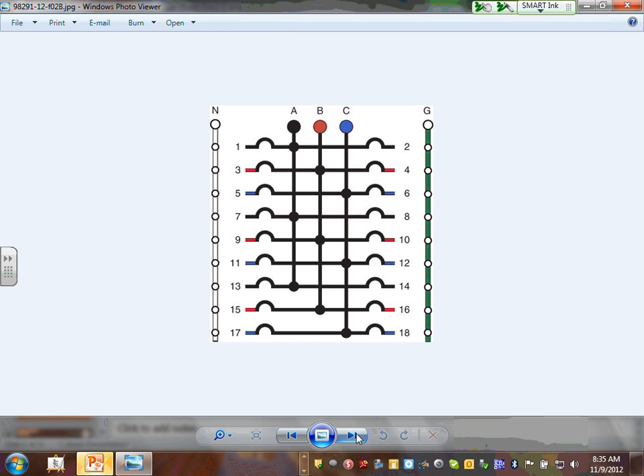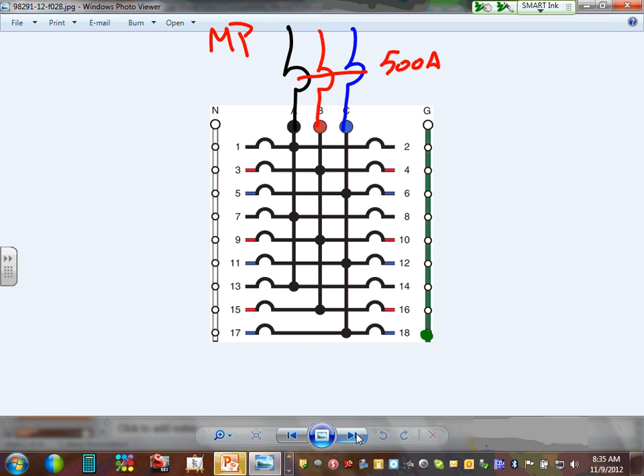Let's put a circuit breaker here, guys, and make it my main panel. Right on the spot here, Chad. Circuit breaker, and circuit breaker, and circuit breaker here. And this is my 500 amp main panel. Now, Jeff, since it's a main panel, I want to go bond what? The neutral to where? To the ground. This is my main bonding jumper, and I want to take the ground to where? To Mother Earth. Can I have thumbs up, Chad? This is how you do it in a main panel. One more time. Phase A, phase B, phase C, neutral, ground. This is how it looks when you open it.